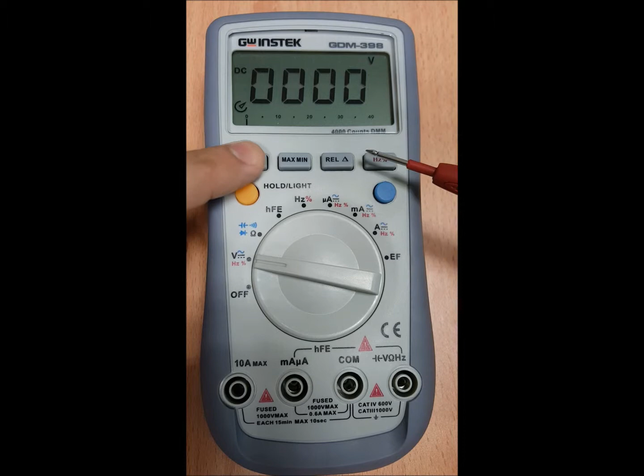With regards to range, which works basically in all the different options, by clicking the range we are going to change between the available ranges. So clicking the range will change the multimeter from auto ranging to manual ranging. Now, for example, we can get volts, and you can see the location of the point. Now volts without any points, millivolts, and keep pressing, and this will go into a loop, changing the accuracy and the range. If you would like to go back to auto range, you will need to click on range for a few seconds, and that will get you back to auto range.